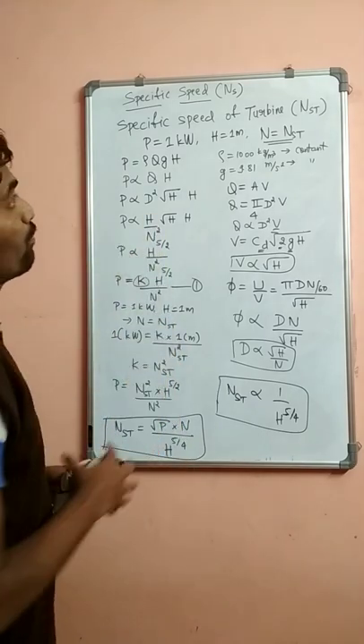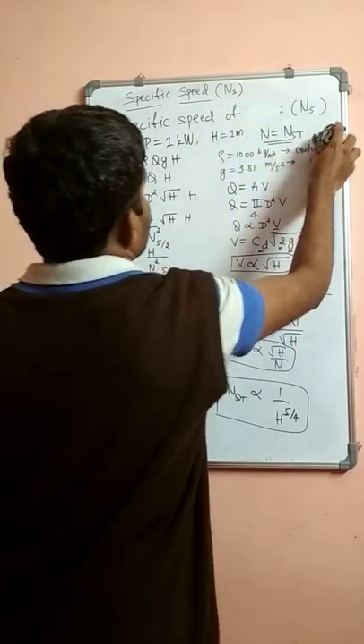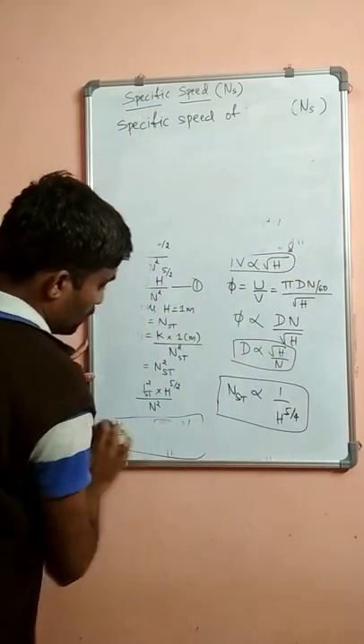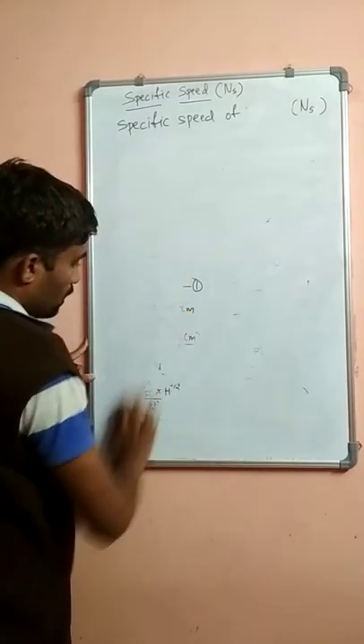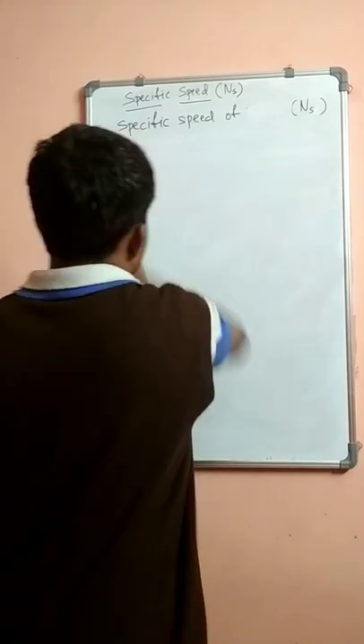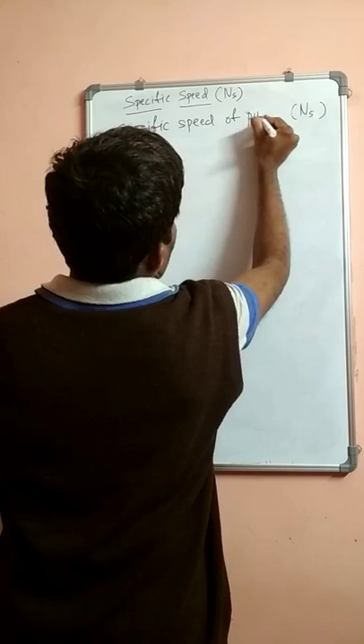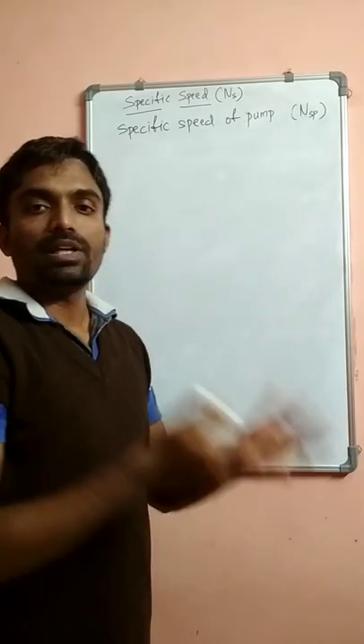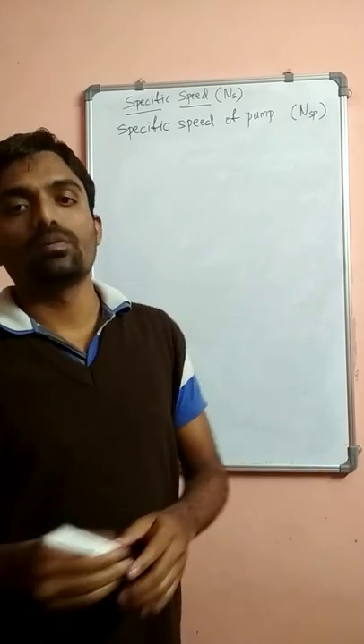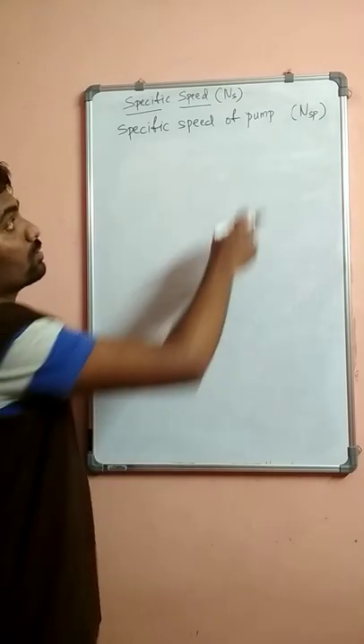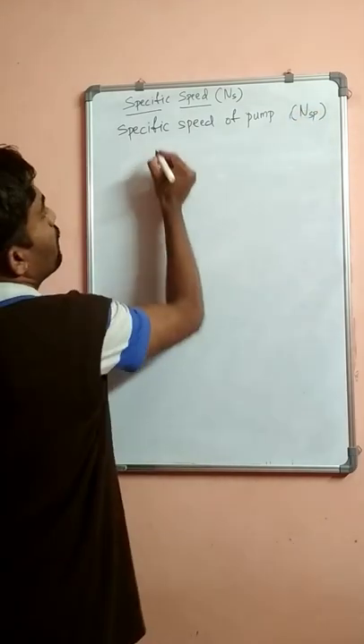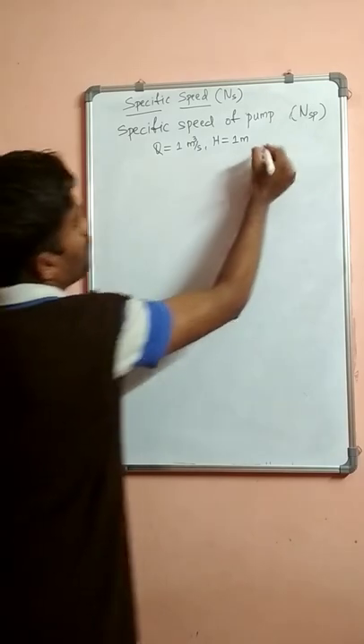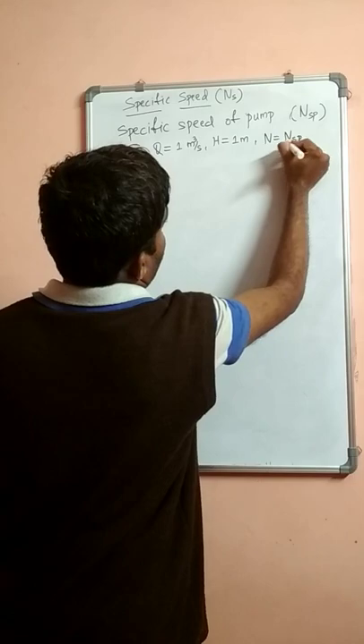Now let us discuss about Specific Speed of Pump, denoted N-S-P. We can define it similarly: it is a pump which is geometrically similar and reduced in size compared to the actual pump, which is giving 1 meter cube per second discharge at a head of 1 meter. In that case, the speed of the pump is called the Specific Speed of the pump.